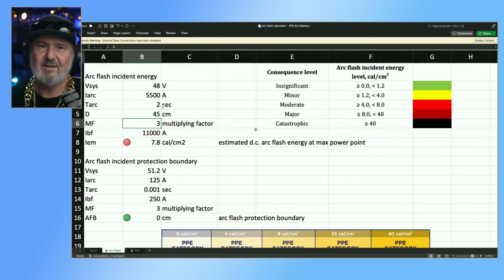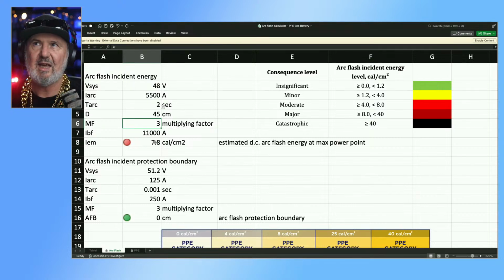Whoa. So that means this lead acid battery can't go, because it's section 6 and the arc level is above 4 cal per square centimetre, it can't go in a building under the roof that contains habitable rooms. So it can't go in an attached garage, for instance. It can go in an external building because it's under 8 cal, but only just.